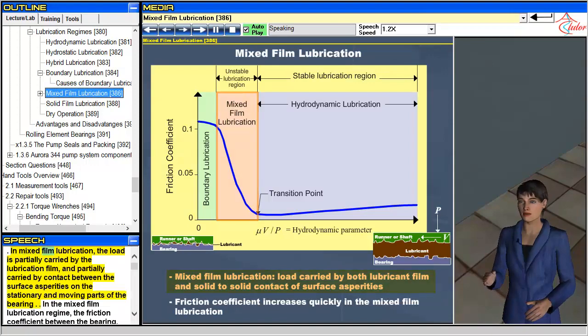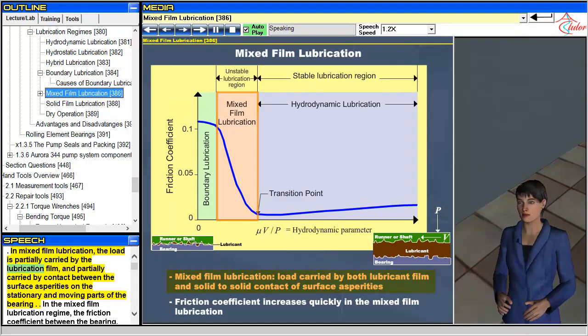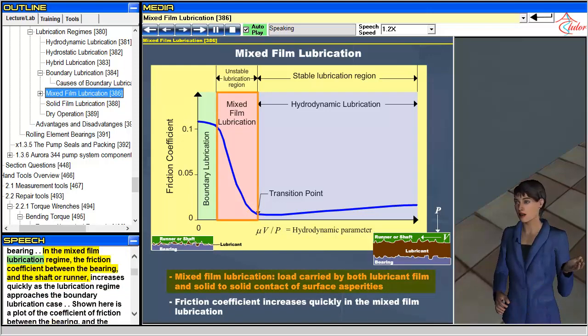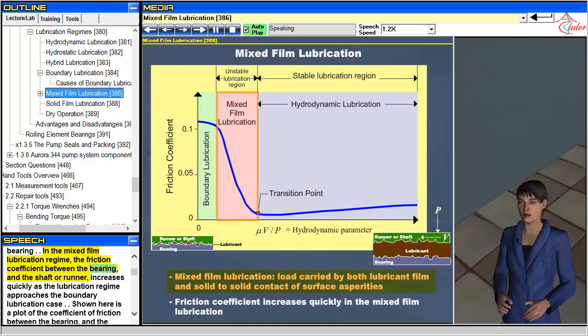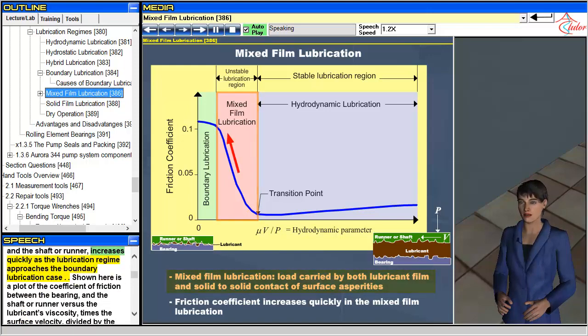In mixed film lubrication, the load is partially carried by the lubrication film and partially carried by contact between the surface asperities on the stationary and moving parts of the bearing. In the mixed film lubrication regime, the friction coefficient between the bearing and the shaft or runner increases quickly as the lubrication regime approaches the boundary lubrication case.